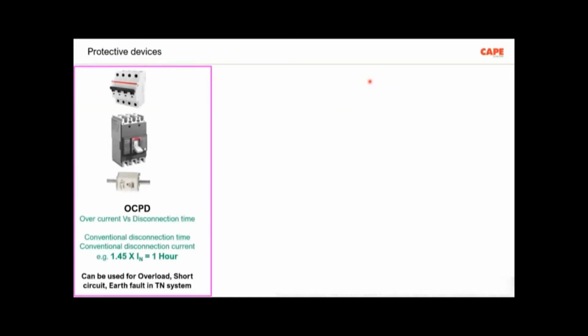Now, protective device. In each of these problems, the protective device is supposed to work and it is supposed to disconnect the supply within a certain time. You have no other option. The only option is that your protective device should trip. For that, we have different kinds of protective device. The first one is of the category OCPD, overcurrent protective device. That means an MCB, MCCB, fuse, and so on. Now, once you select this protective device, of course, the current rating, there are several measures. For example, if you select an MCB, what is the load requirement, then the sizing of the conductor shall be calculated based on the load requirement. The sizing of the MCB has to be calculated based on the size of the wire, and so on.